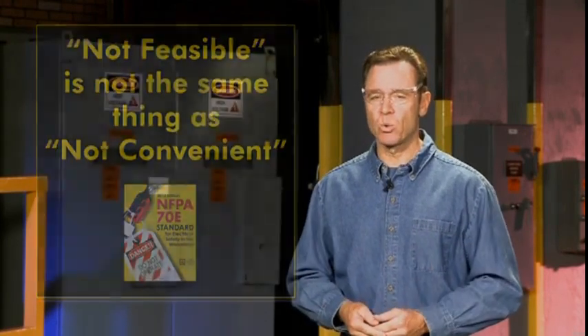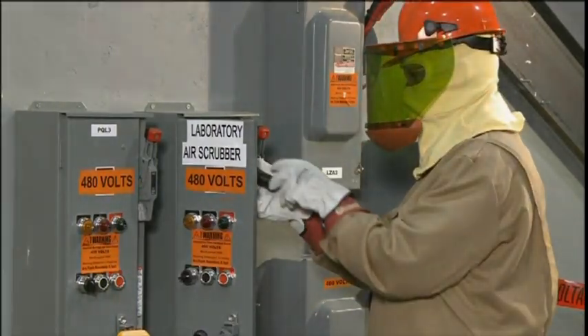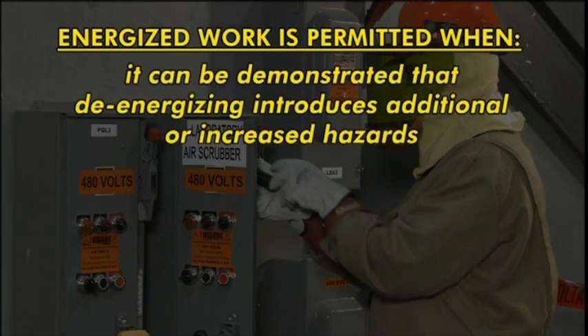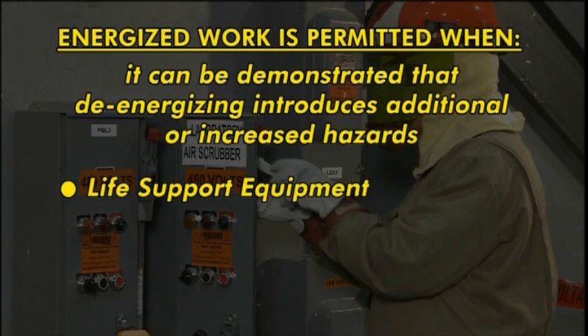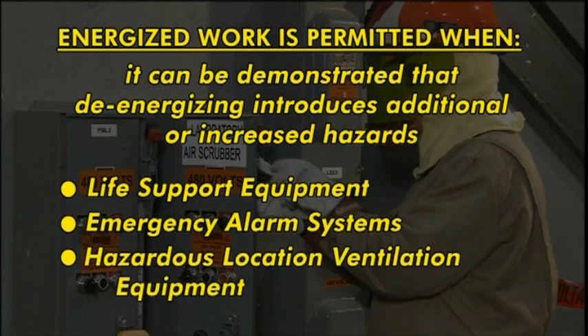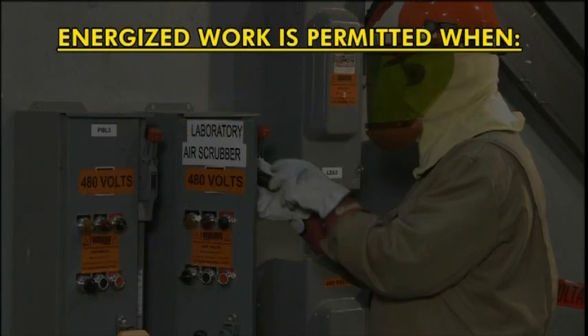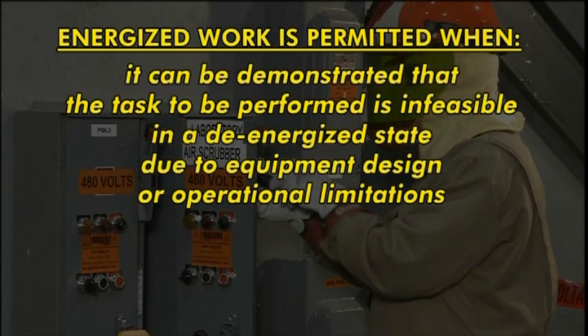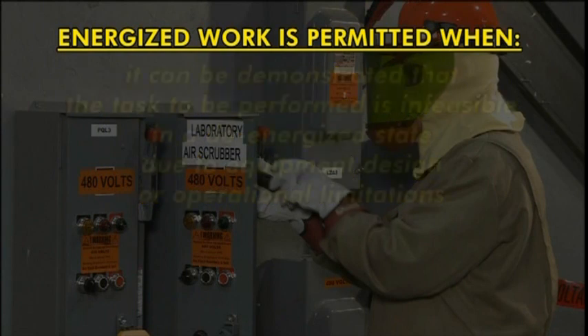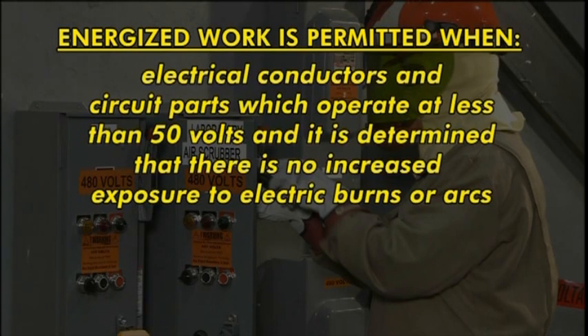The regulation allows energized work to be performed under the following limited conditions. Energized work is permitted when it can be demonstrated that de-energizing introduces additional or increased hazards. Some examples include life support equipment, emergency alarm systems, or hazardous location ventilation equipment. Energized work is permitted when it can be demonstrated that the task to be performed is infeasible in a de-energized state due to equipment design or operational limitations. Energized work is permitted on electrical conductors and circuit parts which operate at less than 50 volts, and it is determined that there is no increased exposure to electric burns or arcs.